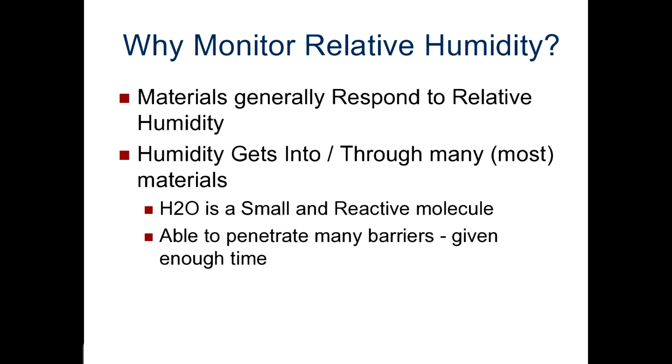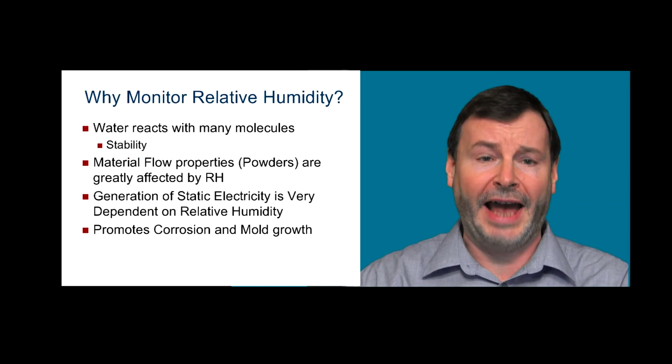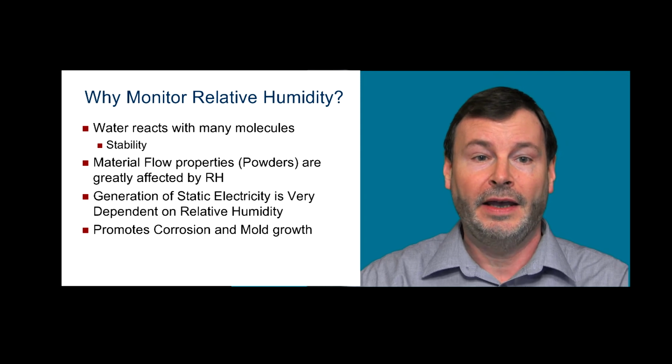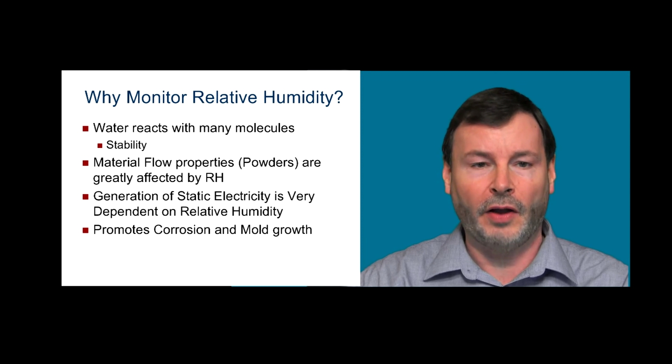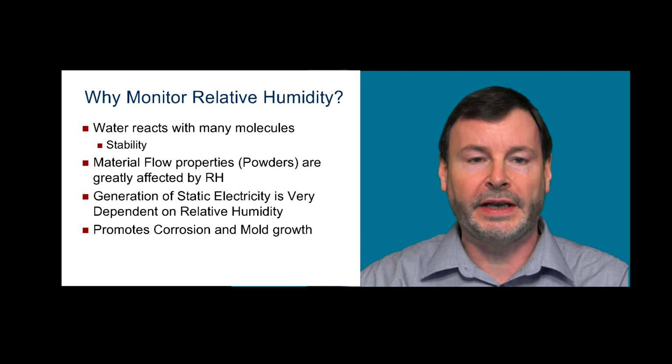Materials generally respond to relative humidity, not absolute humidity. We'll talk about the differences a little later. Humidity can get into and through most materials and barriers. Water molecules are very small, they're very polar and reactive. Water reacts with so many molecules that it's actually called the universal solvent. And that's why we engage in stability testing, to understand how water molecules will react with a given product or material, and also how water is able to get through a barrier of some kind.